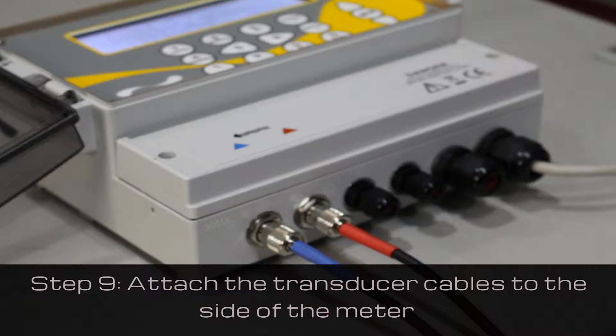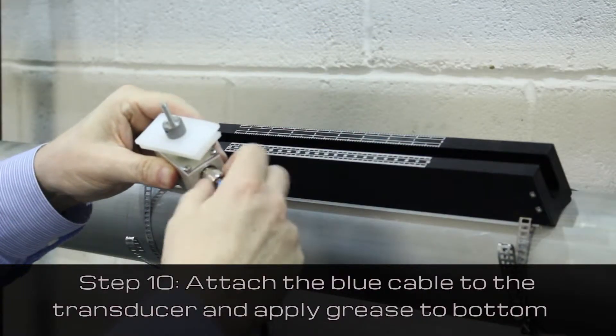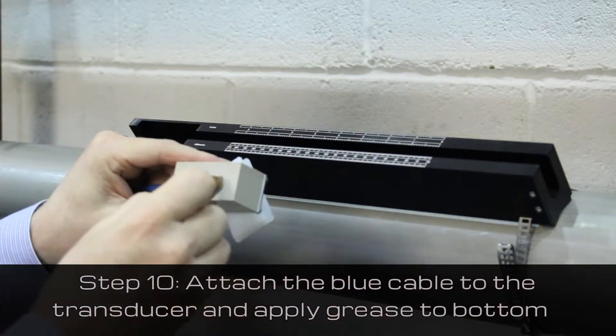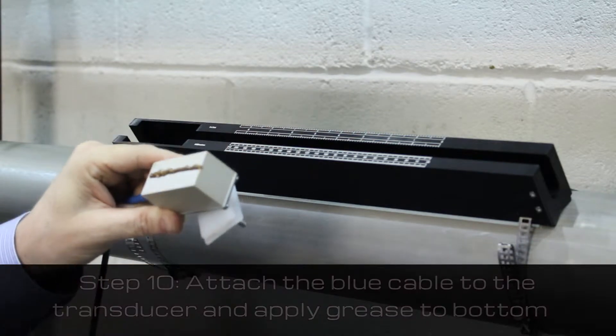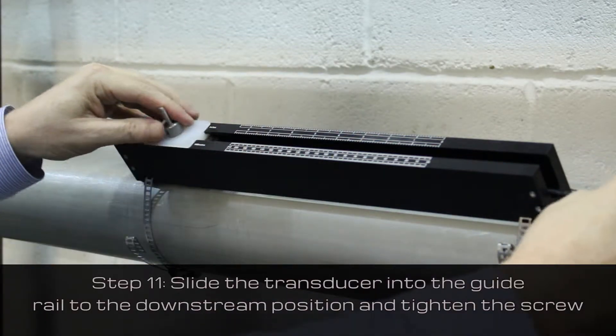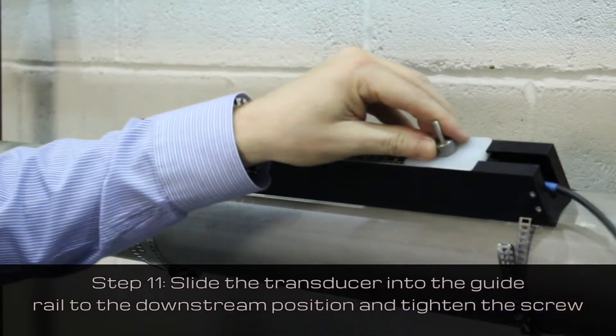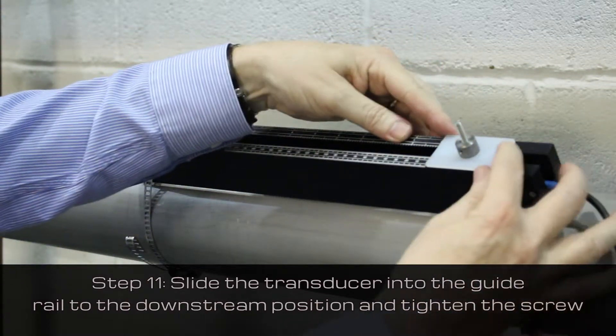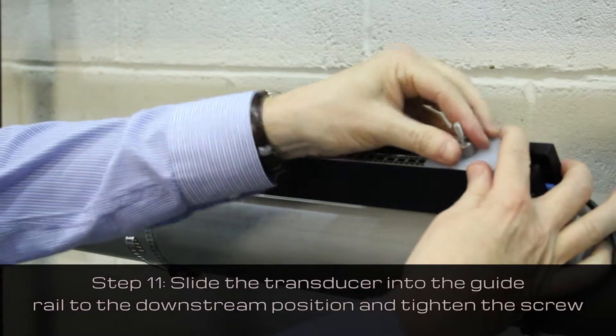Attach the transducer cables to the side of the meter. Attach the other end of the blue cable to the transducer, apply grease to the bottom and slide the transducer into the guide rail in the downstream position and tighten the screw.